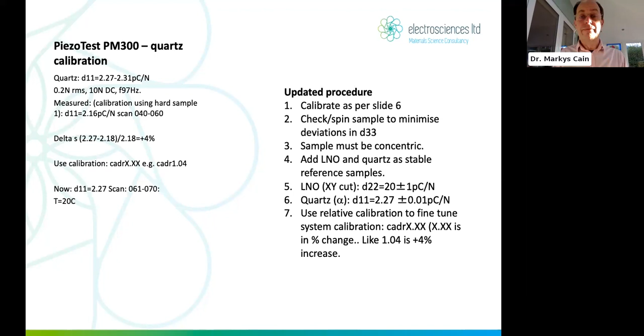And of course, it's not necessarily such a great thing to do, is it? Because of course, most materials are in the hundreds. So how on earth do you calibrate? You're calibrating all the way down at 2 or 3 picocoulombs per Newton, but you're taking measurements at hundreds. Well, the next best thing is lithium niobate. You can do the same thing with lithium niobate, which gives you 20, so you've got an order of magnitude. And then the next best thing is, well, you have to use a hard composition piezo material that you have calibrated independently using interferometric methods or resonance methods. That's pretty much the only way of doing it. But bear in mind, you do a resonance, you're measuring it at hundreds of kilohertz. Okay, so the frequency is different.